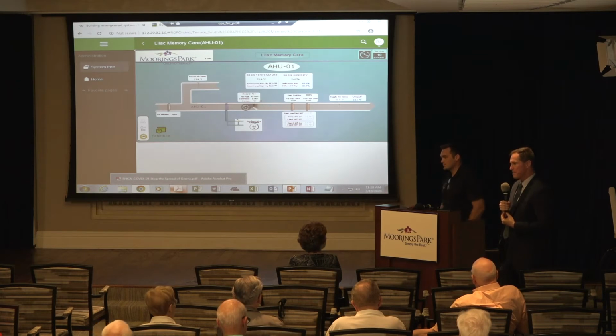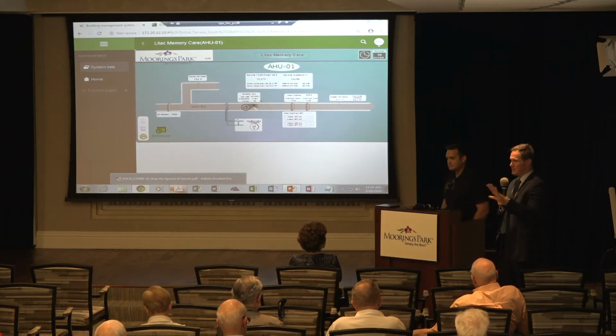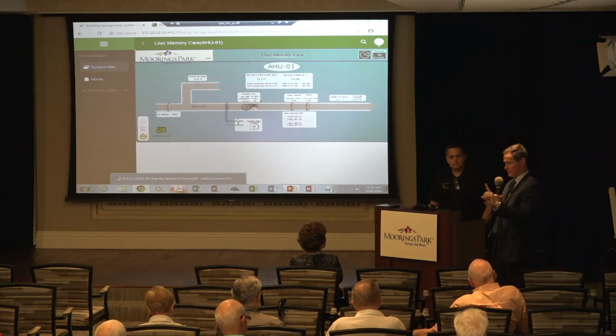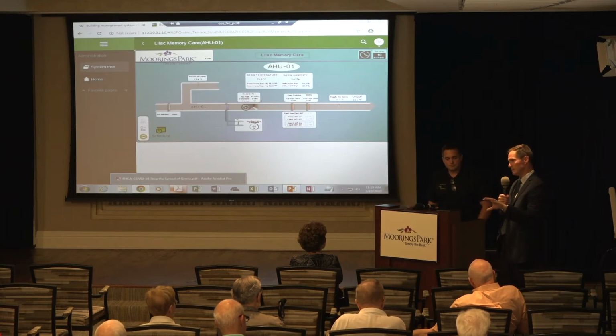And when that goes down, our generators kick in automatically. So we have ATSs, automatic transfer switches, in all of our generators. Those generators only power, in the AL units, our elevators, our fridges, and one outlet per unit. We can't power the street lights, pedestrian lights, or lake fountains — none of that. It's just really the critical items within a unit.